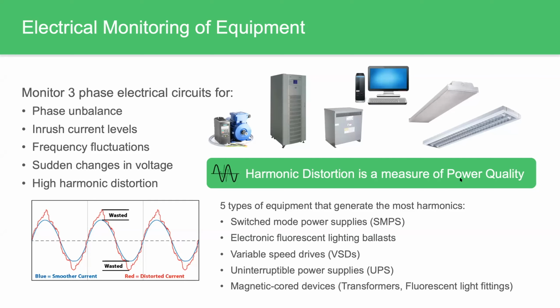Some power quality disturbances come into your facility from the utility, but many electrical problems are actually caused within your own electrical distribution system. There are at least five culprits—types of equipment that generate harmonics from within your system. Anything with a switch mode power supply, lighting ballasts, variable speed drives, UPSs, and anything with a magnetic core introduces harmonics into your system. These are things to watch out for, because high harmonic levels not only reduce overall power efficiency but also have many other negative impacts on equipment.